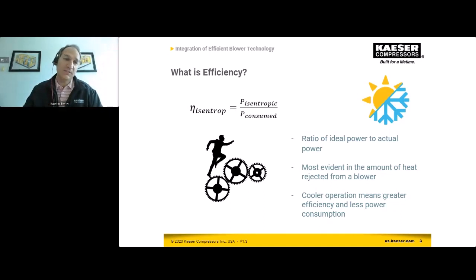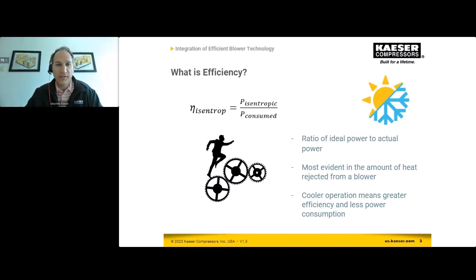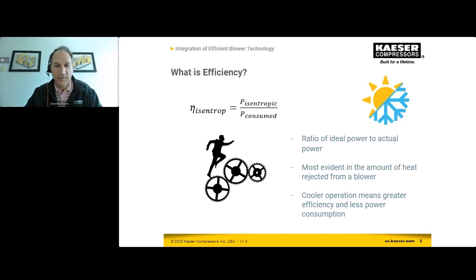When we talk about isentropic power, which is kind of your ideal power mathematically — if you throw in your pressure and your flow into a formula, you get what we call isentropic power — and you divide that by your real power, which you're actually consuming at that flow rate from the machine. This becomes what we call isentropic efficiency.